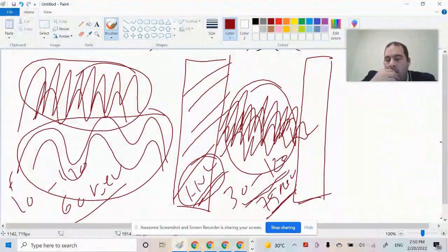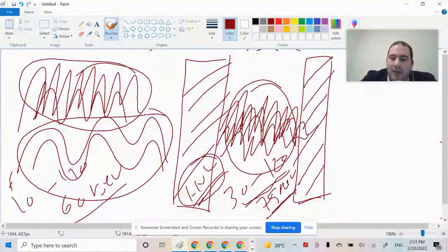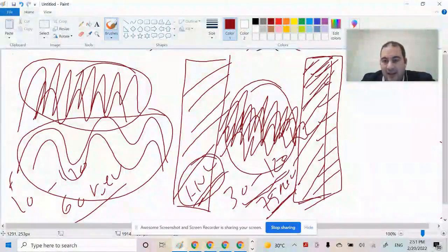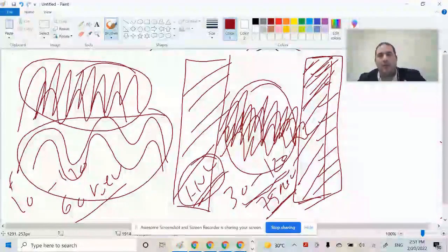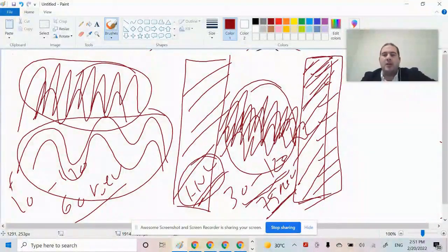Of course, to stop this energy effectively and efficiently, I need a larger thickness, meaning my second half-value layer must indeed be larger. This is indeed what happens. In fact, the second half-value layer with polyenergetic beams is significantly larger than the first one, because photons that passed through initially underwent beam hardening, removing all soft radiation and only allowing high energy radiation to pass through.